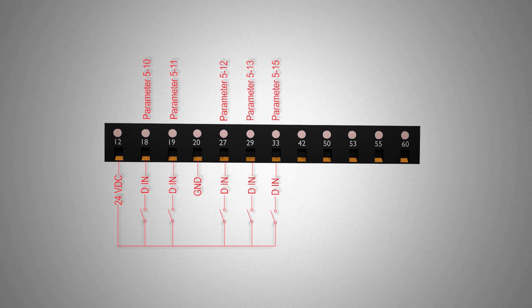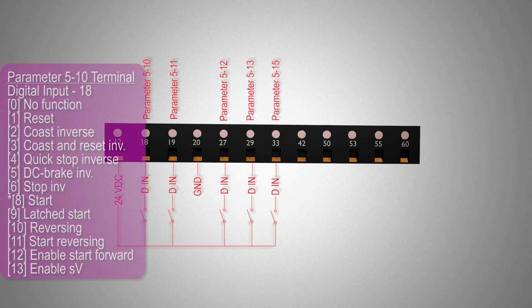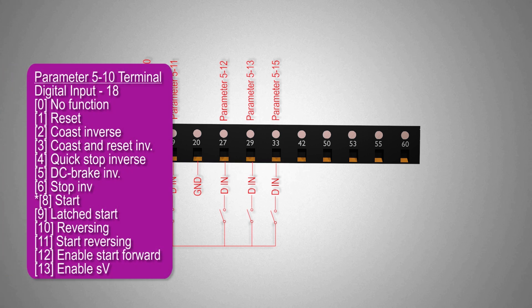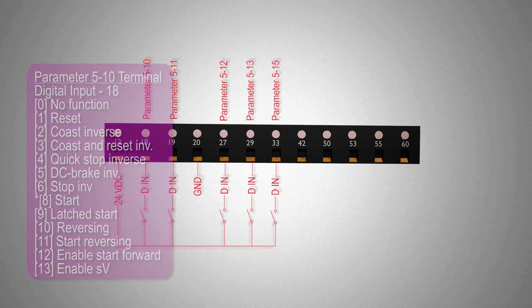Terminal number 18 to terminal number 33 are the digital inputs. These inputs are programmable as per our operation requirements. Parameters 5-10 to 5-15 are used to program functions like start, stop, reverse and reset errors for these digital inputs.